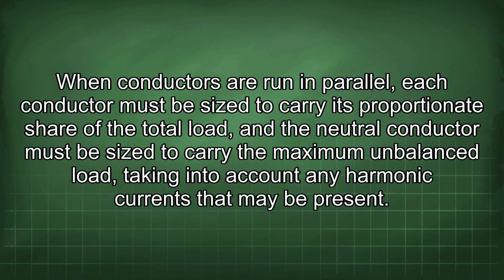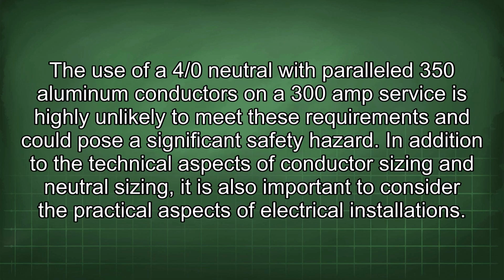When conductors are run in parallel, each conductor must be sized to carry its proportionate share of the total load, and the neutral conductor must be sized to carry the maximum unbalanced load, taking into account any harmonic currents that may be present. The use of a 4/0 neutral with parallel 350 aluminum conductors on a 300 amp service is highly unlikely to meet these requirements and could pose a significant safety hazard.